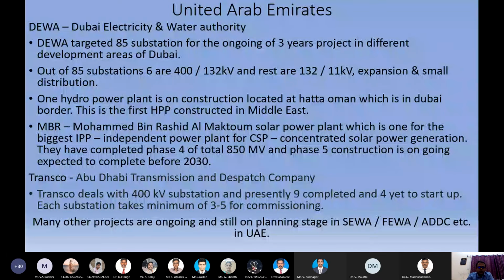Out of these 85 substations, we have 6 at 400 kV. A 132 kV substation construction phase to commissioning phase will take around 24 to 28 months - actually it's 32 months but reduced to 24-28 months. Still, it depends on geographical conditions, working locations of contractors, and other factors. And for a 400 kV substation, it will solidly take around 4 to 5 years each, including expansion and small distributions as well.